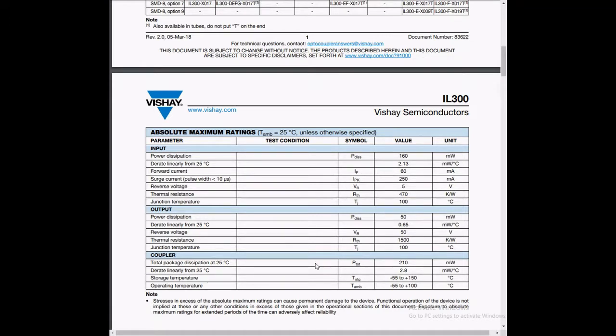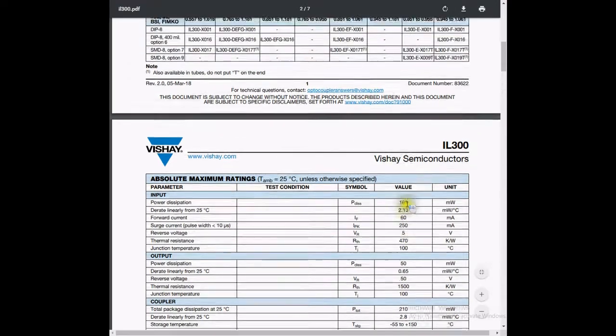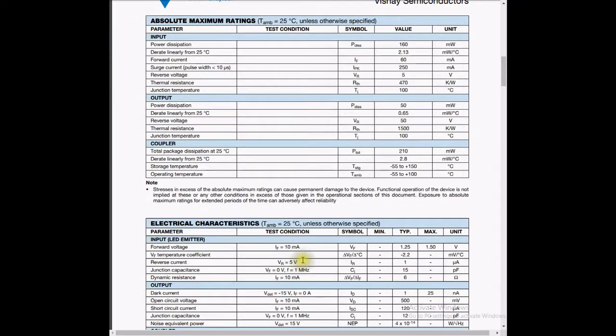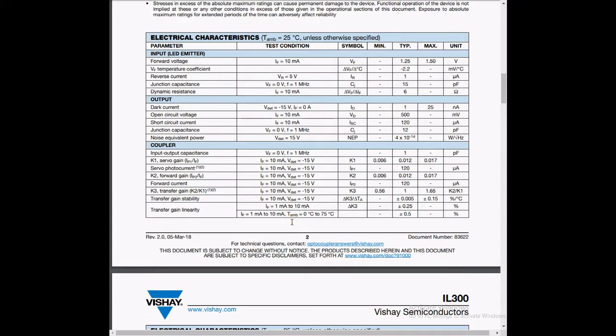And part of getting all this certified is the cost of having someone come down and rip this apart and measure all the gaps, measure all the creepages, clearances, looking at the chips. If there's a chip they're not quite sure about, say the power supply, they can't find all the correct details, then they will rip that power supply apart very carefully and measure it. Even when you have a mains transformer that's rated to medical, if they don't trust the paperwork, they will physically rip your transformer to pieces, taking detailed measurements of wrappings of cables, covering insulation, material types, flammability. They'll do everything to it, and if they're happy, they then sign it off. So this can cost many thousands and thousands of pounds to get something like this through certification.